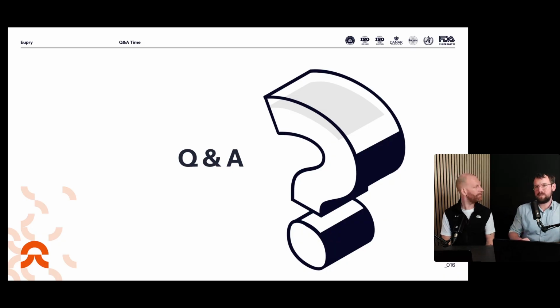Not in terms of the URS, that's my view on it at least. You should write a URS for the requirements of the HVAC system. The actual implementation should be any rooftop units or any sort of HVAC system that satisfies those requirements. Where it does have an impact, and where we often see it, is that if you have large changes to your control systems, for example the HVAC system, you would sometimes, as a bare minimum, need to reassess or review whether you need to perform temperature mapping again. Often you would end up in this situation if you choose a different brand or a different capacity or larger changes. Often, even though it's the same name and brand and specification, you would need to requalify or remap.